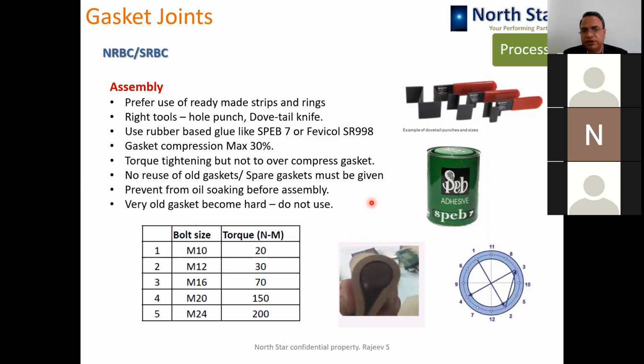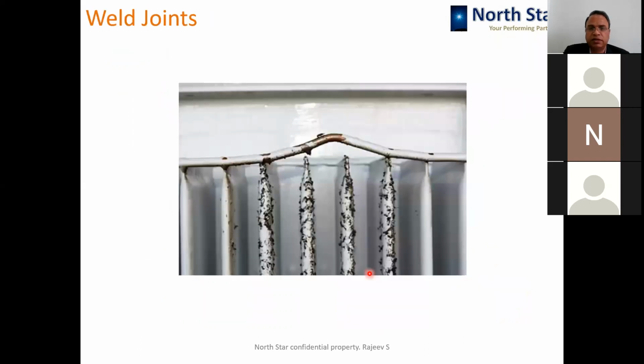Gaskets are a perishable item; they become hard with time. So you can do this small hardness check of the gasket. Bend it around a 20 mm diameter rod - if it is cracking or breaking, you can consider the gasket old and throw it away.